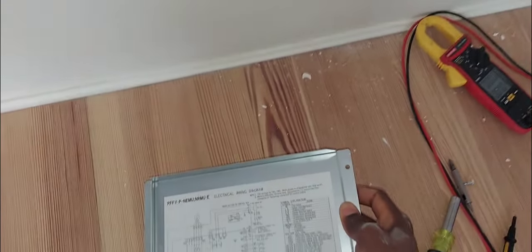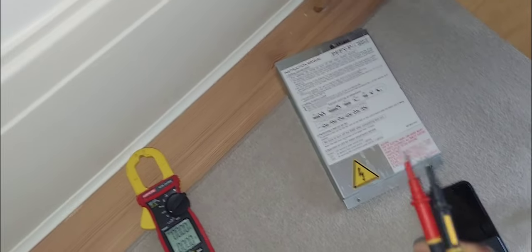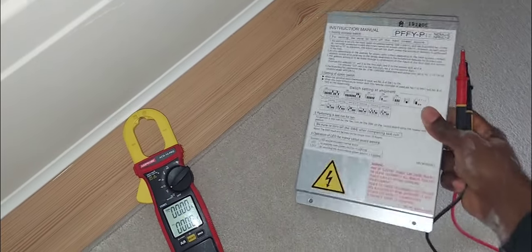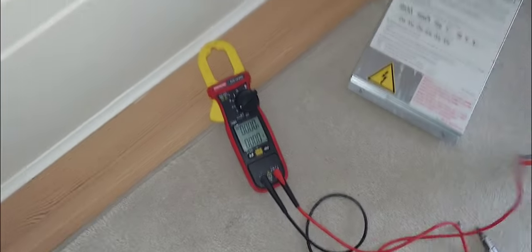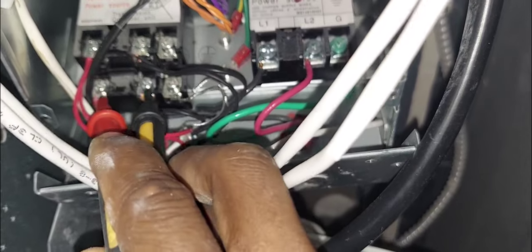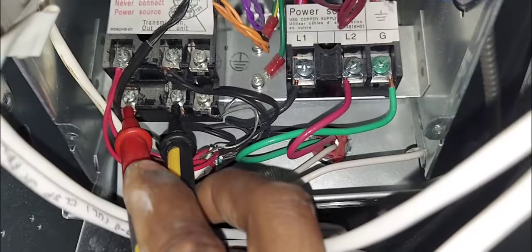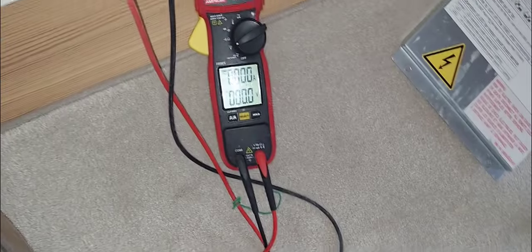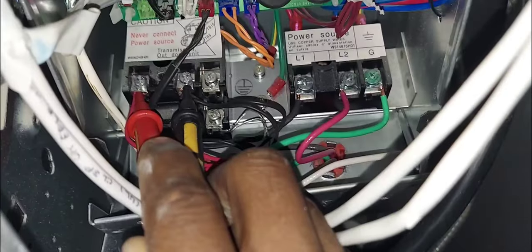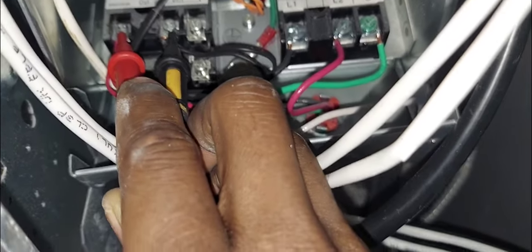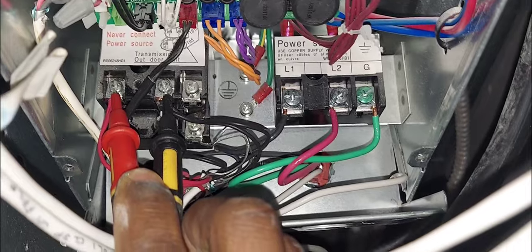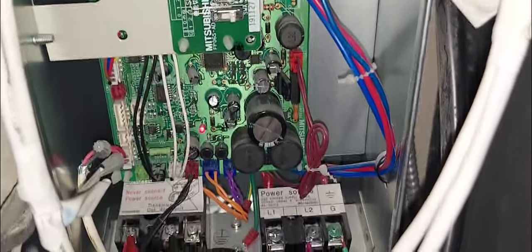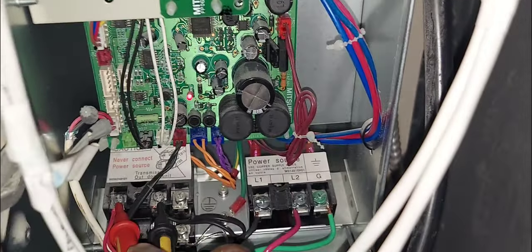Now here is a similar situation, it's another unit, there's a cover so I'm going to do it again, go in there. This is a better view so I'm doing it for you guys. You can see there's a better view right here, better access. Bottom terminal right there, you can see that's your Mnet and no volts. If I go on the top terminal, the top two terminals right here that go to your remote controller, that's 12 volts that get powered from this board right here. You can see there's a red light on there, so it's good, there's power there, there's power coming to the unit right here and 11.8 volts.